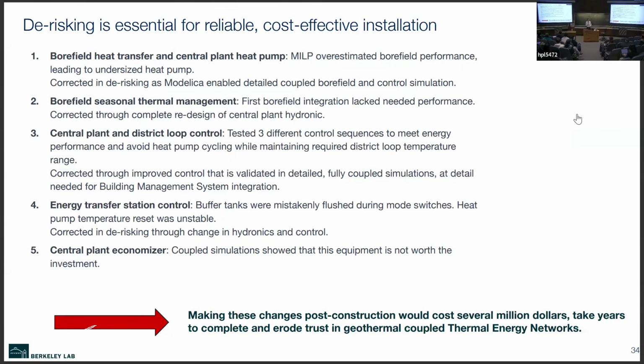The energy transfer station control mistakenly flushed the buffer tanks, so again we lost performance there. The heat pump temperature reset also had to be changed because it was unstable at first. We corrected that control in this de-risking step.